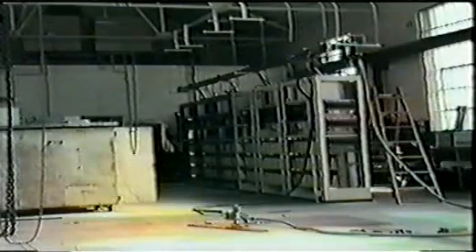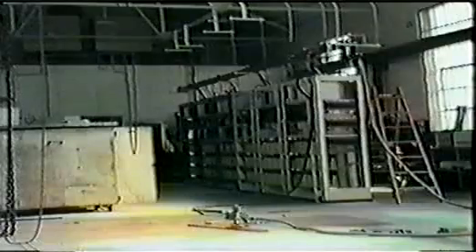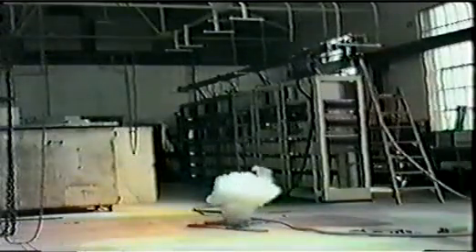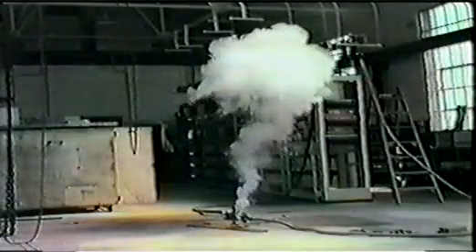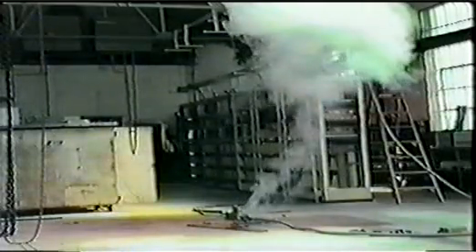The following simulates a 200-amp cable connected across the output of six racks in parallel. It looks as though all the output current shunts have fused. So let's go and have a look at the damage.